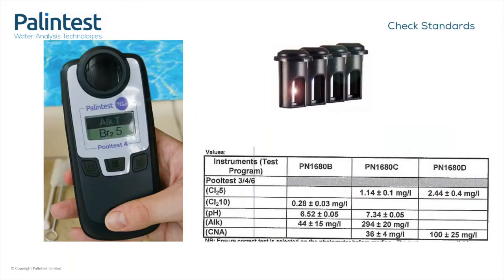To use NDF standards, simply select the tests listed on the certificate. In this example, let's assume it's alkalinity. The instrument will read the NDF standard exactly the same as if it were a real sample, and convert the percent T to an alkalinity reading, which you can then check on the certificate.